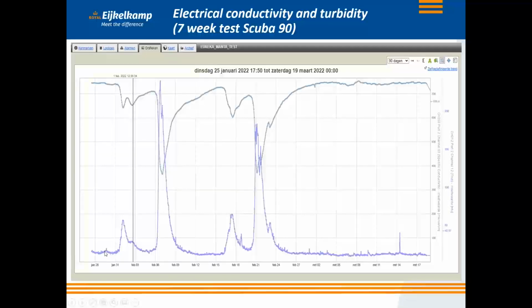We started approximately at an NTU of 10 or 15, and also we ended with approximately 10 to 15 NTU. So that indicates that the probe is still clean after 7 weeks of operation and isn't disturbing the measurement. The wipers on the sensor circulate before each measurement.